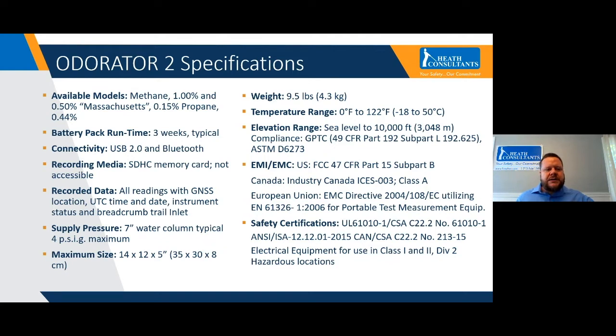I also want to talk a little bit about the supply pressure. Within the manual, we recommend a 7-inch water column as a typical inlet pressure for natural gas, but this device does require a maximum of 4 psig gas inlet pressure. So if you are doing an odorant test on a system higher than 4 psig, you'll want to also carry a step-down regulator with you that can be installed between your gas system and the Odorator 2 to bring the pressure down below 4 psig.